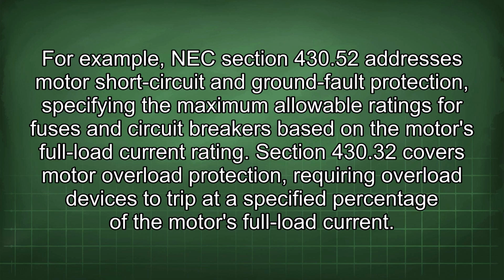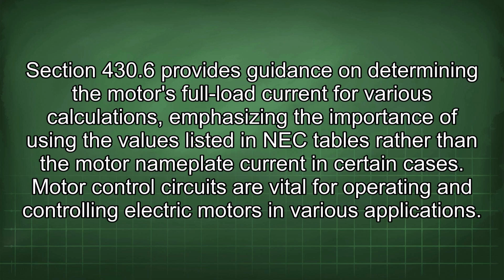Section 430.32 covers motor overload protection, requiring overload devices to trip at a specified percentage of the motor's full load current. Section 430.6 provides guidance on determining the motor's full load current for various calculations, emphasizing the importance of using the values listed in NEC tables rather than the motor nameplate current in certain cases.